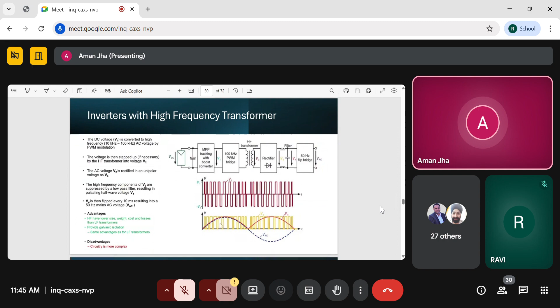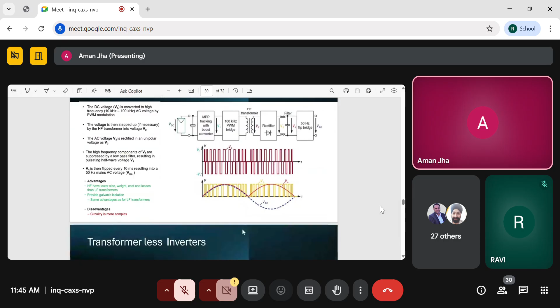And this again just shows how the transformer is used, how it works through the first stage and second stage, and finally we get the output at this level. Coming to transformer-less inverters, they are much more popular. Being power electronics, here you have more work to do because galvanic isolation is not there, so you have to take care and make some RCD arrangement so that if there is some earth leakage, the system does not fail.